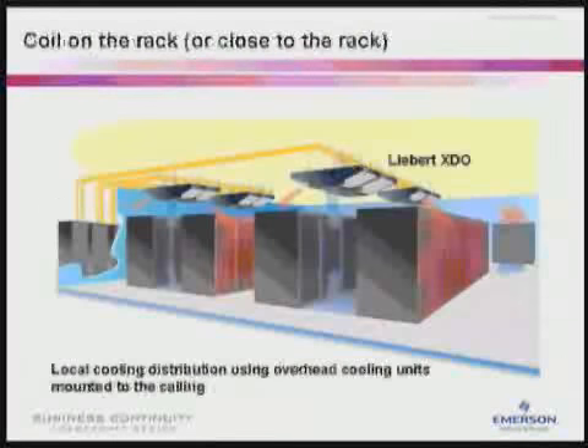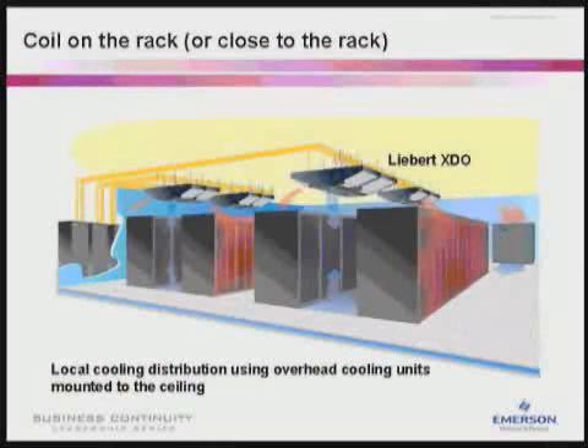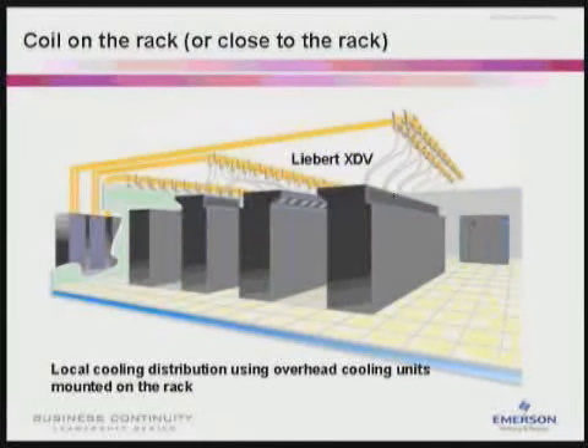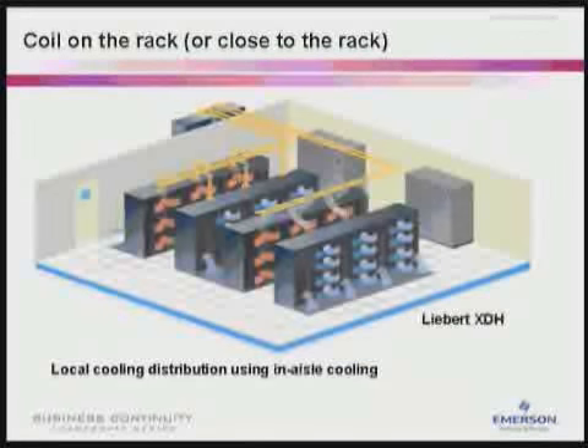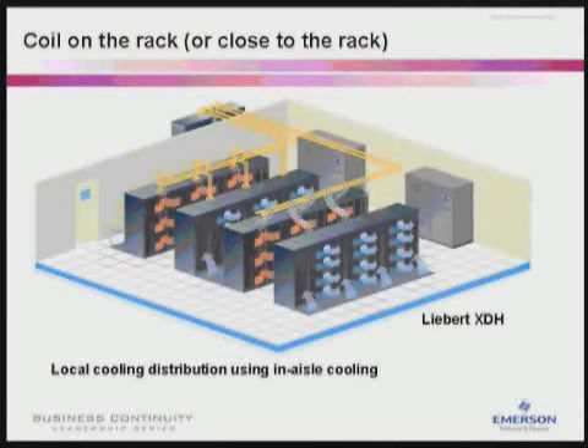Here is a depiction of local cooling using overhead cooling units mounted in the ceiling. High availability methods are used by employing redundant cooling loops. Here is a depiction of local cooling using overhead cooling units mounted on the rack. Again, redundant cooling loops are employed. And here is a depiction of local cooling using in-row cooling. In all of these configurations, local cooling supplements base load cooling to help deal with high heat density applications. All use a hot aisle, cold aisle approach.